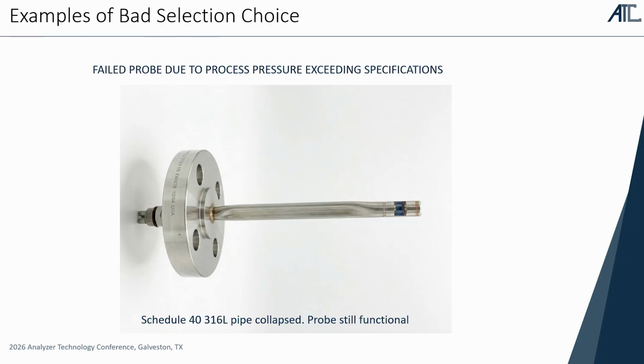Here's an example of a probe that was brought to above its design pressure. It might be a little bit hard to see, but that should be a 316 Schedule 40 pipe sticking out of that flange. It's crushed. There are actually fiber cables in there. What was interesting about this is the probe was actually still useful. It didn't break the probe itself, it just crushed the pipe. But somebody missed a specification.